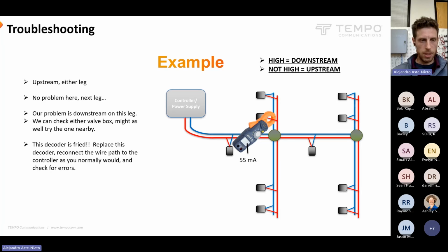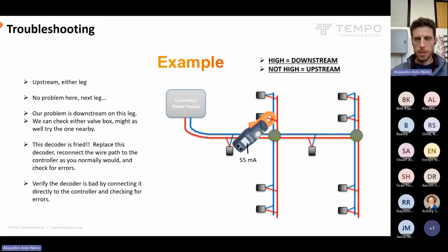So let's replace this decoder and reconnect to the wire path and see if we're all good. And we can also just take that decoder, plug it into the controller, see if it gives us errors there, and we can verify that it was the decoder that was the issue. If this had just been a bad splice, this would have been kind of a normal number over here, and all the high current would have been traveling through the dirt between these 2 wires at these bad splices. But we measured this actual decoder wire and verified that it contained the problem.